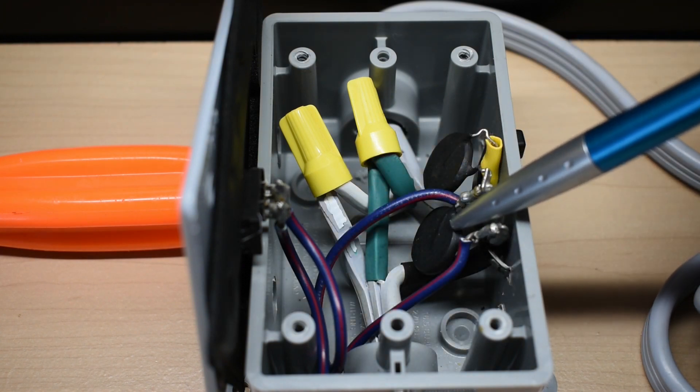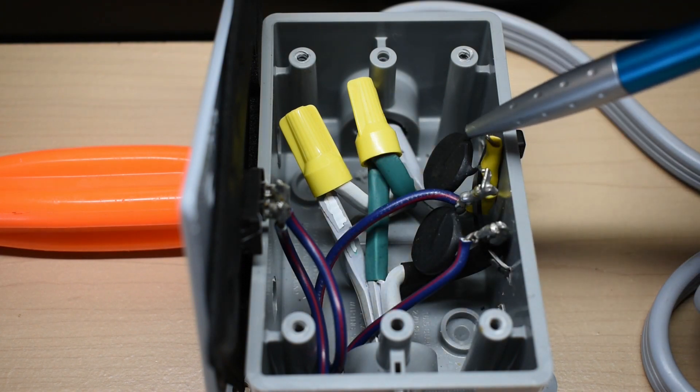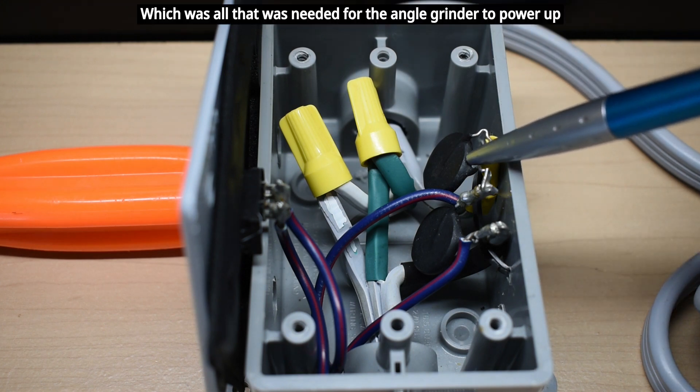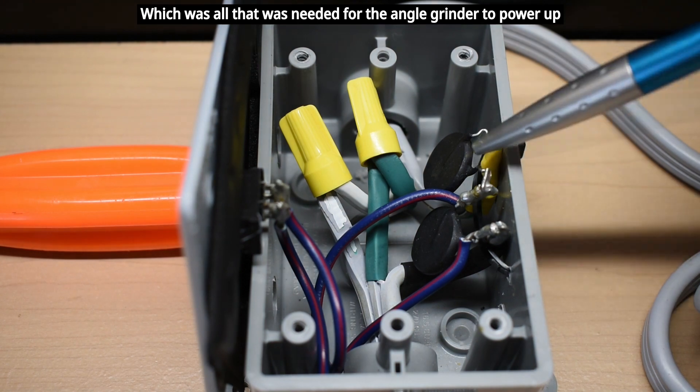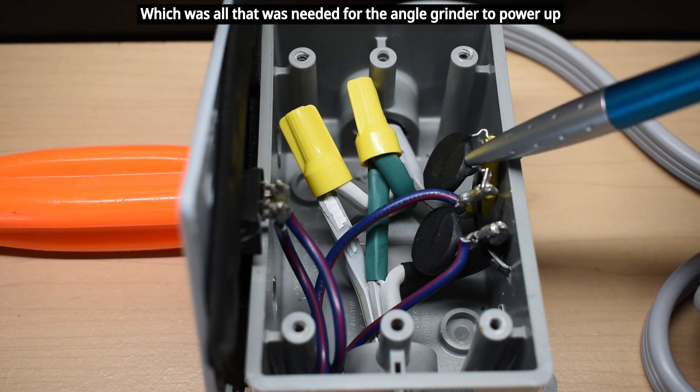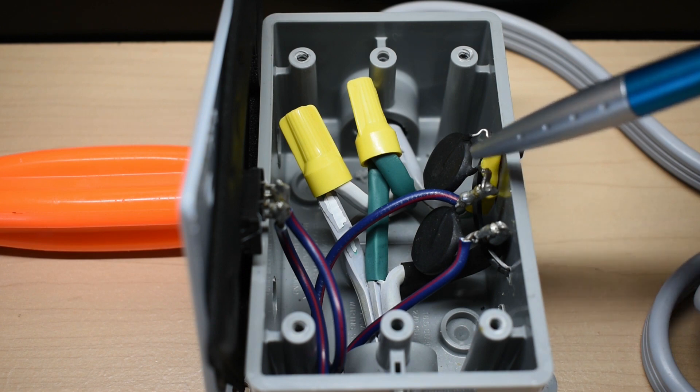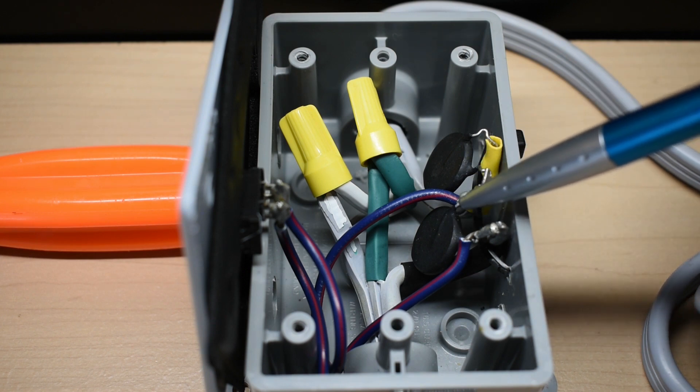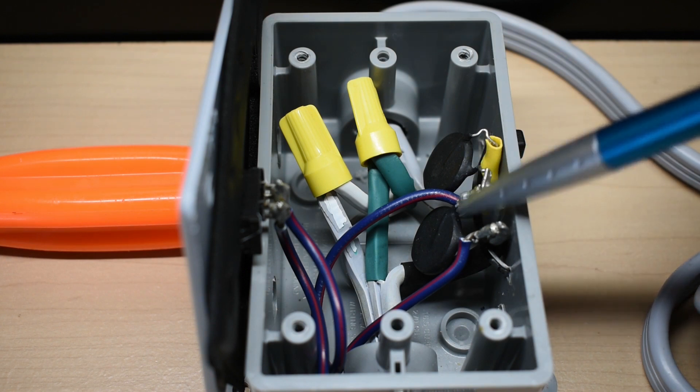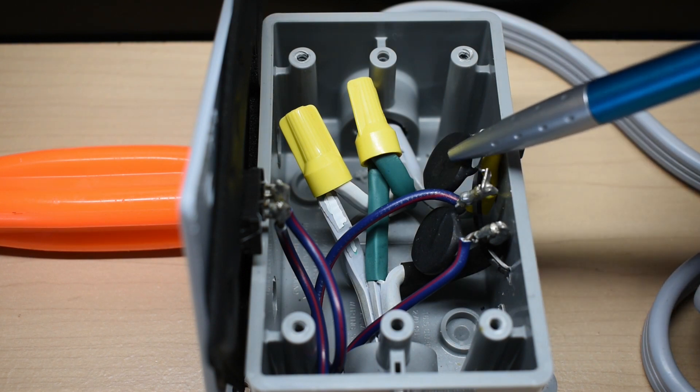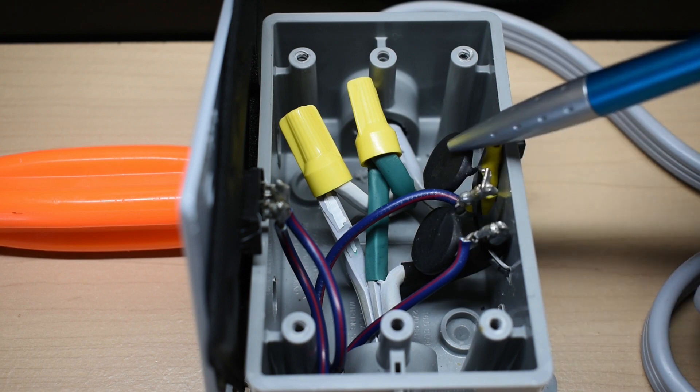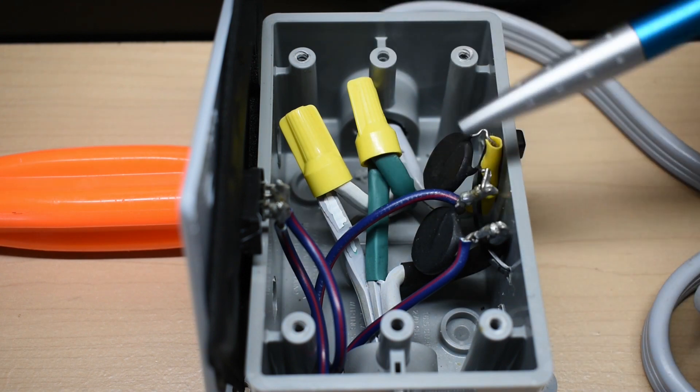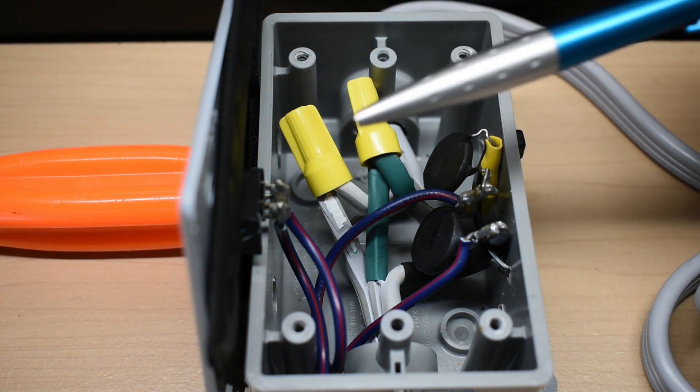So when I put it in the low position, I'm only going to be having 5 ohms of resistance added to the circuit. But if it's not enough and the device does not power up or the inverter goes into overload, then what I'm going to do is add on an additional 5 ohms. So we're going to have a total of 10 ohms of resistance.